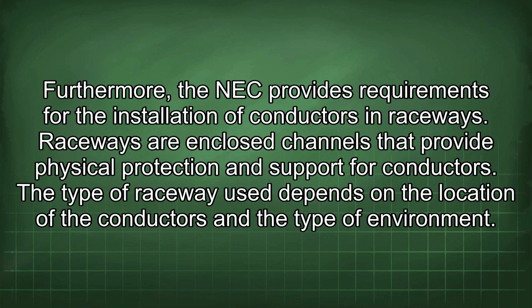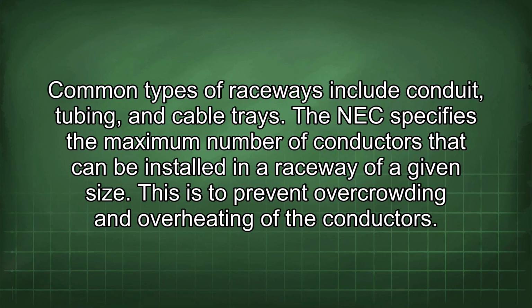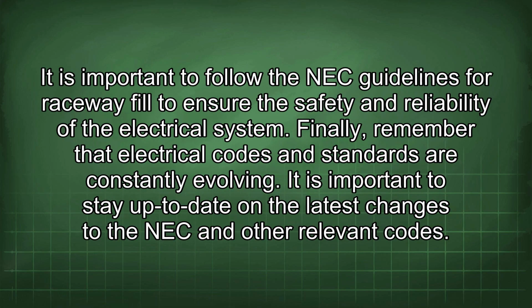Furthermore, the NEC provides requirements for the installation of conductors in raceways. Raceways are enclosed channels that provide physical protection and support for conductors. The type of raceway used depends on the location of the conductors and the type of environment. Common types of raceways include conduit, tubing, and cable trays. The NEC specifies a maximum number of conductors that can be installed in a raceway of a given size. This is to prevent overcrowding and overheating of the conductors. It is important to follow the NEC guidelines for raceway fill to ensure the safety and reliability of the electrical system.